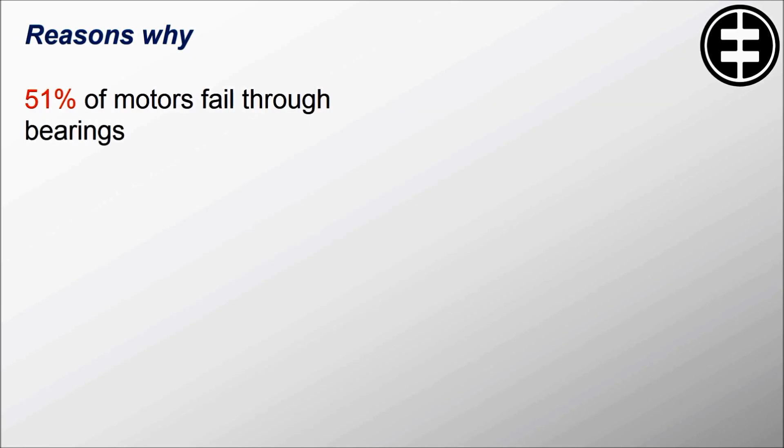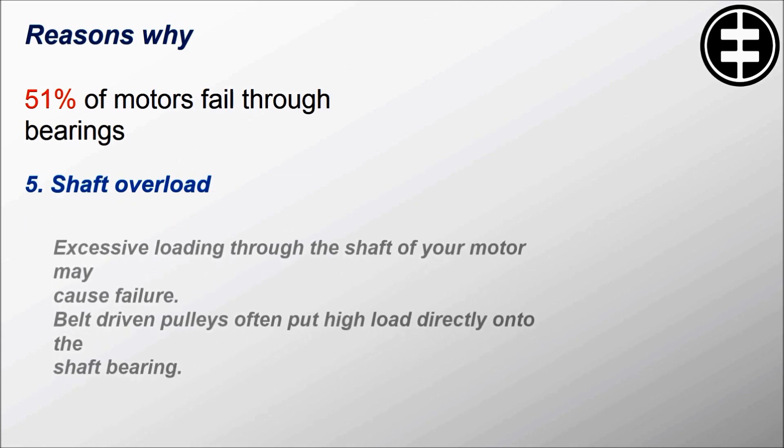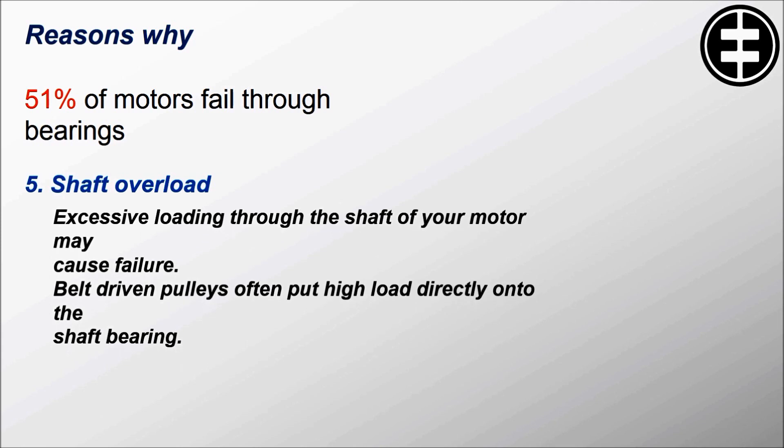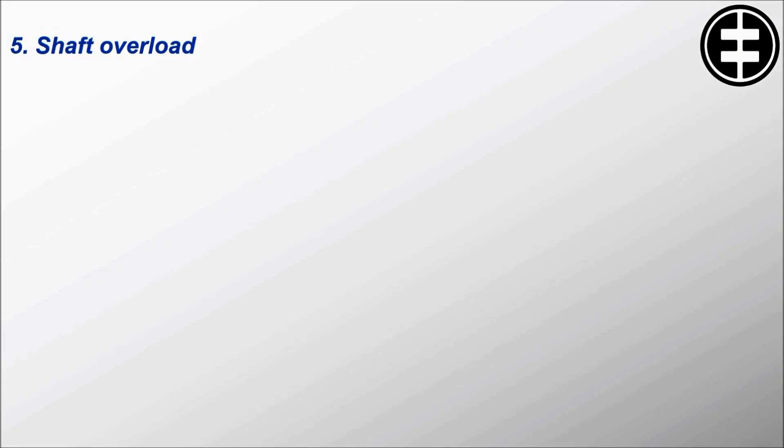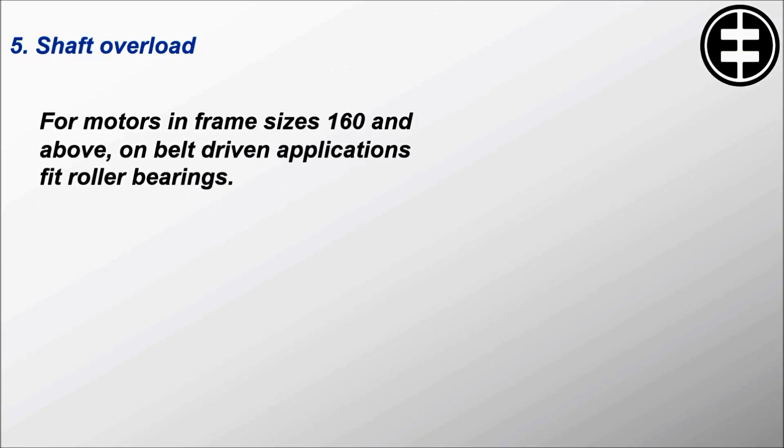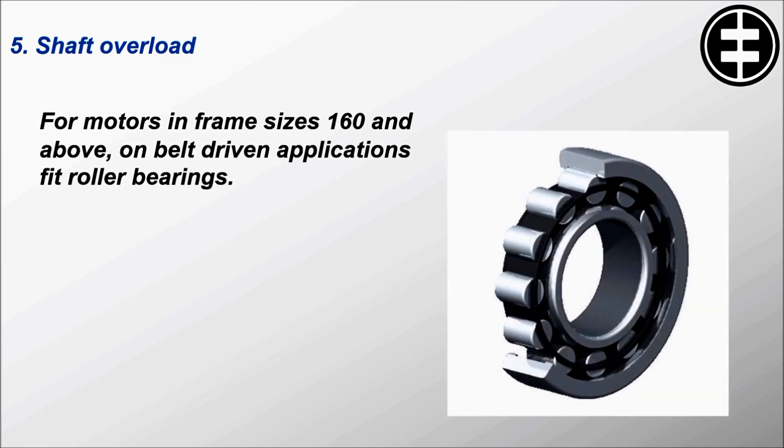Reason number five is shaft overload. Excessive loading through the shaft of your motor may cause failure. Belt-driven pulleys often put high load directly onto the shaft bearing. For motors in frame sizes 160 and above on belt-driven applications, fit roller bearings to deal with the expected shaft overload.